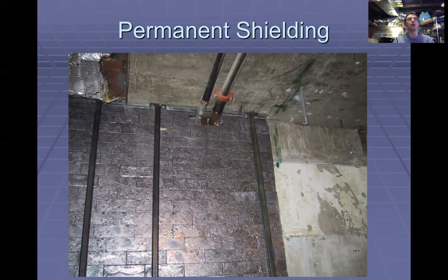I know when Monmouth was being built, we did a survey on a PET CT room where they had been designed well and everything, but then at the last minute, I guess they drilled a hole for something that was going to be above the room. And sure enough, when we did the survey, one spot on the floor in the room above had a pretty high reading, because they had jeopardized the shielding in that area. So they had to open up the walls, add a little more shielding, and make sure it was in compliance. And that's stuff that we look for when we do surveys.